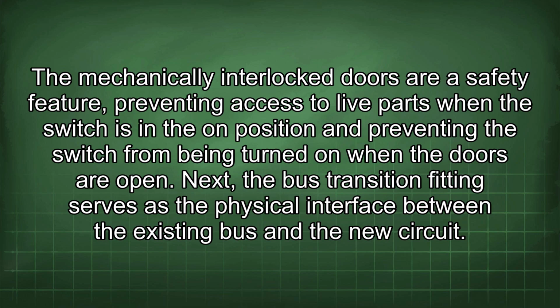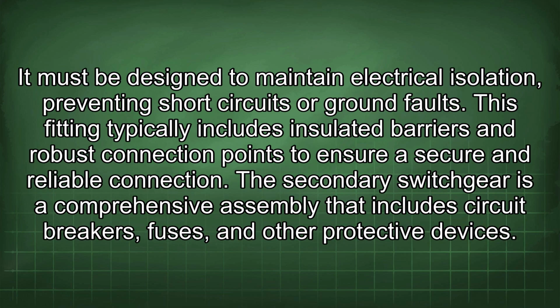Next, the bus transition fitting serves as the physical interface between the existing bus and the new circuit. It must be designed to maintain electrical isolation, preventing short circuits or ground faults. This fitting typically includes insulated barriers and robust connection points to ensure a secure and reliable connection.